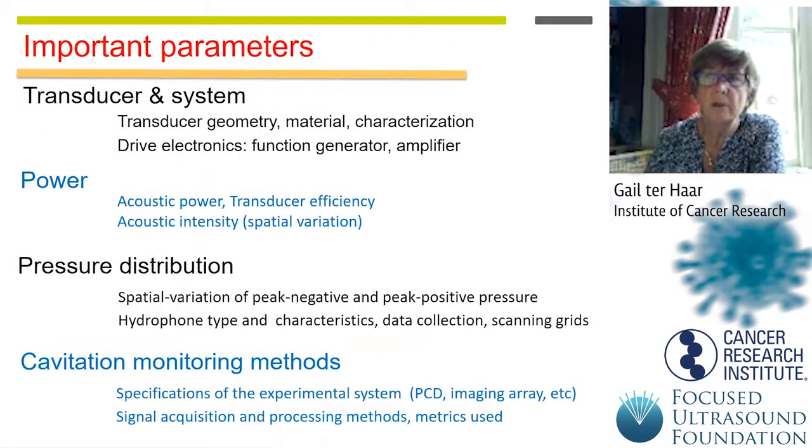The important parameters, well, the transducer and its system, as I've said. We need to know about the transducer geometry, the material of the transducer, how it's characterized, a bit about its drive. We need to know about the acoustic power as a function of setting for the devices we're using and how that's being measured. And we'd like to have information about the spatial variation of the acoustic intensity.